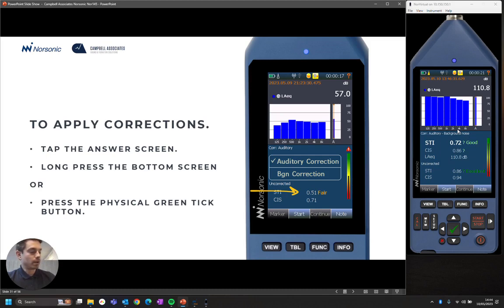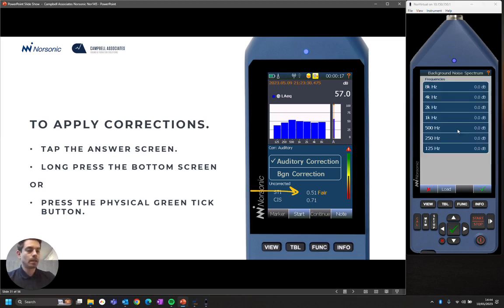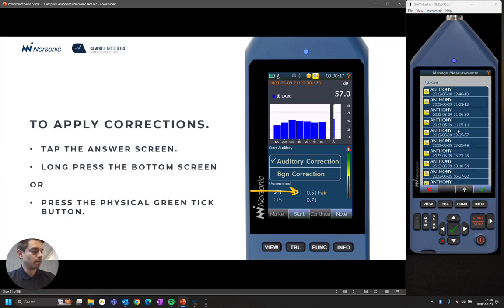We can amend the background noise correction, shall I say, by pressing the tick on the keypad, going to define background spectrum, and then we can enter in individual values. Now, this is a little bit more long-winded to do it this way. Perhaps what we might do instead is just to actually carry out a background measurement using the environmental mode, save that as a file, and then we can just load this into this spectrum here.